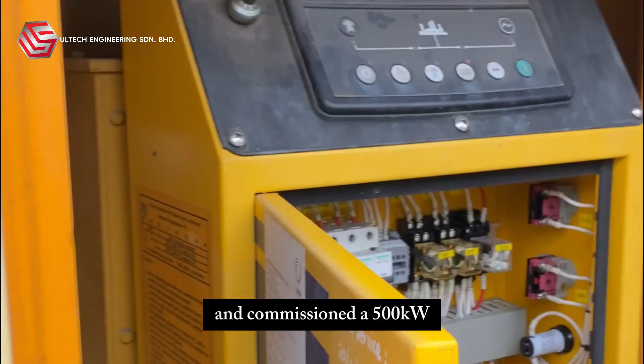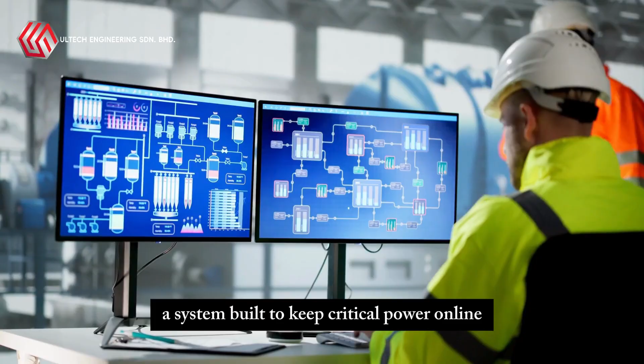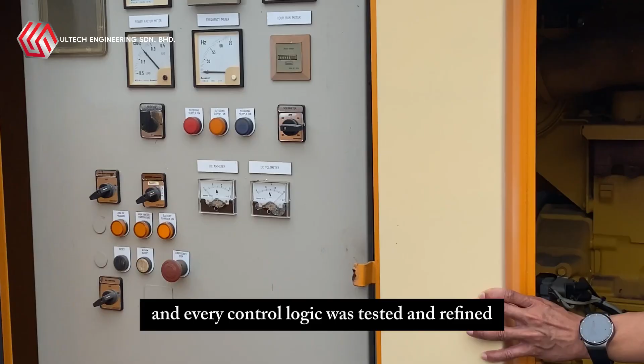This year, at the Seligi platform, our engineers took on the challenge of building reliability where it matters most, far out at sea. We designed, supplied, and commissioned a 500-kilowatt emergency diesel generator control panel, a system built to keep critical power online when every second counts. Offshore environments are never forgiving: heat, humidity, vibration, and constant exposure to salt air. But this project pushed us to innovate for durability. Every cable, every relay, and every control logic was tested and refined to ensure a seamless operation in extreme conditions. The result? A robust system that not only powers emergency equipment, but also reinforces operational safety and confidence for the crews on board.